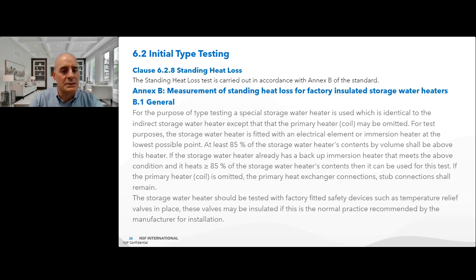For test purposes, the storage water heater is fitted with an electric element or immersion heater at the lowest possible point, with at least 85% of the storage water heater's content by volume above this heater. If the storage water heater already has a backup immersion heater that meets the above condition and it heats greater than or equal to 85% of the storage water heater's content, then this can be used for the test.